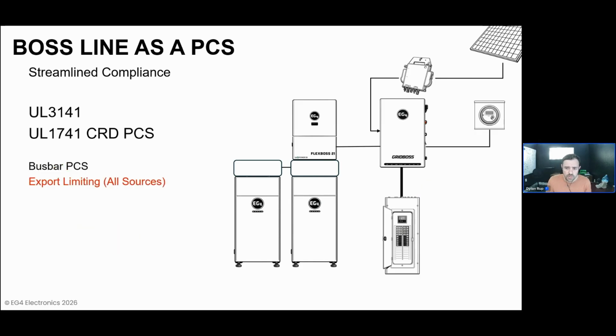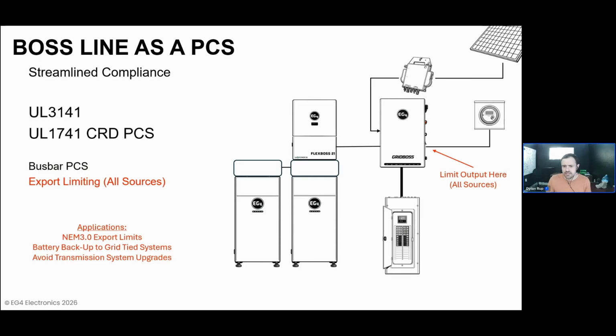Now, the other situation that we commonly see is export limiting across all sources, which is a similar functionality, but now instead of limiting power delivery to the main panel to protect the busbar, we are limiting the output back to the utility connected to the system. Applications here are varied, but what we commonly see is limitations on NEM 3.0 export limits, where the AHJs or the utilities in California don't like to see more than 10 kilowatts of continuous output.